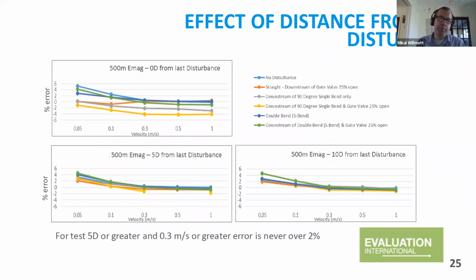So a question we get, and probably the most frequent question, is how far do I need to be away from a disturbance? Now, a disturbance is anything that will distort the flow. It can be a fitting, it can be a bend. And Evaluation International, on this 500 mil rig up in Scotland at the NEL, tested an EMAG meter, an electromagnetic meter, at 0 diameters down from the last disturbance. So that means you have your disturbance, your bend, or a valve that's partly open, and then you put the meter straight after it.